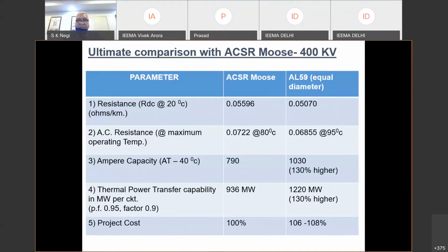Also, we adopted this conductor by changing the design, changing the span of the towers, and used this AL59 conductor in place of ACSR Moose. So this is the example which is available of how AL59 has helped us in enhancing the capacity of the transmission system by carrying out some structural changes and application of the sag tension, spotting of the tower, and how it has helped us to use this conductor and get better performance of the transmission system.